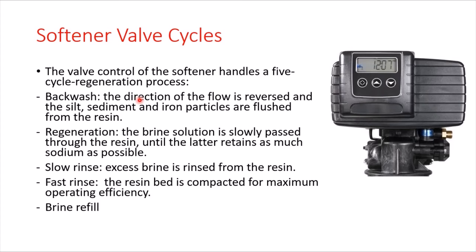At the top of each softener vessel, there is an automatic control valve that controls the five-cycle regeneration process of the resin beads. To regenerate the sodium capacity, we go through five cycles. The first cycle is the backwash, where we clean the resin beads with clean water by reversing the flow direction to remove silt, sediment, and iron particles from the resin. The backwash water must be clean water.